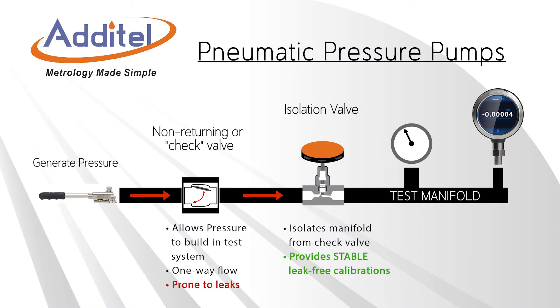A major design feature of all Additel pneumatic pumps is an isolation valve that allows leak-free, stable calibrations. Most pneumatic pumps on the market have non-returning or check valves that allow pressure to be built up in the test volume. These valves are often prone to leakage as seals wear. Additel pumps include a valve that isolates the calibration volume from the check valve, providing stable calibrations even as seals degrade over time.